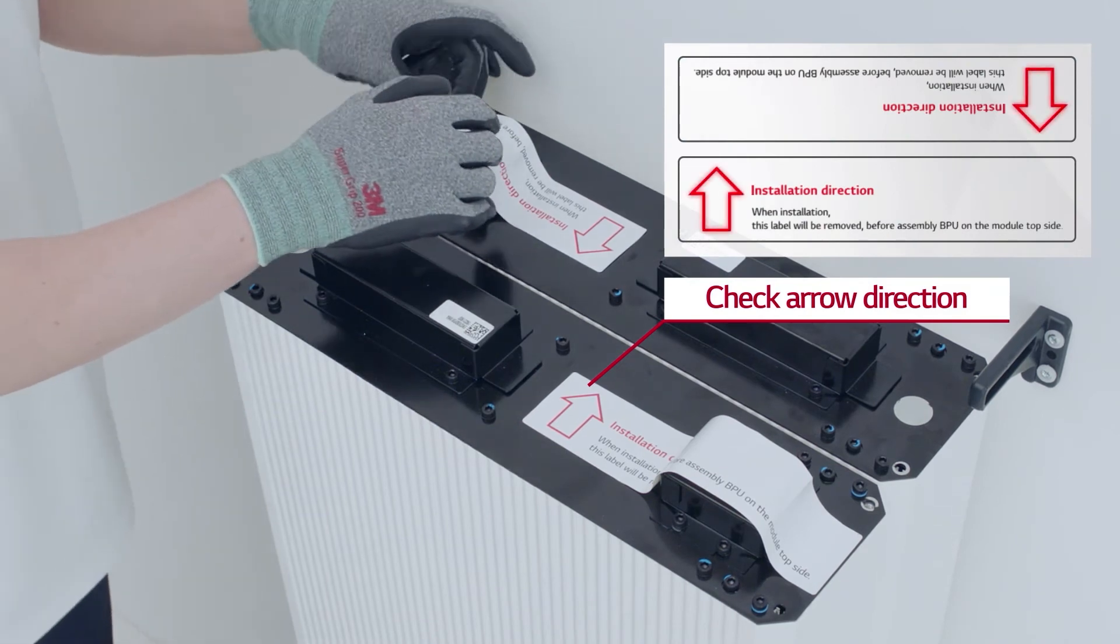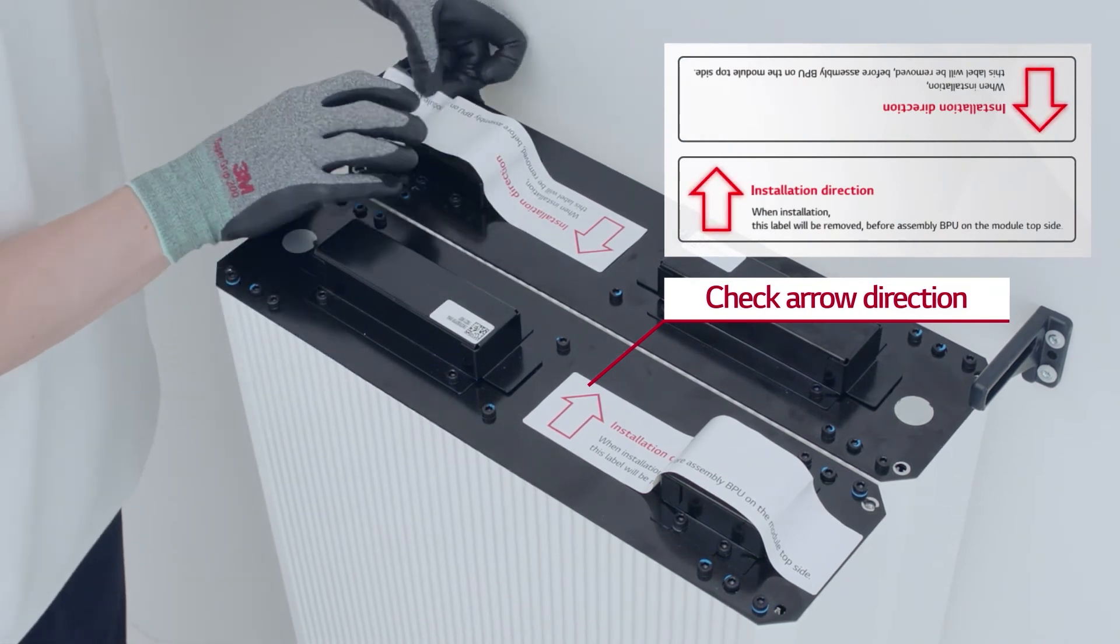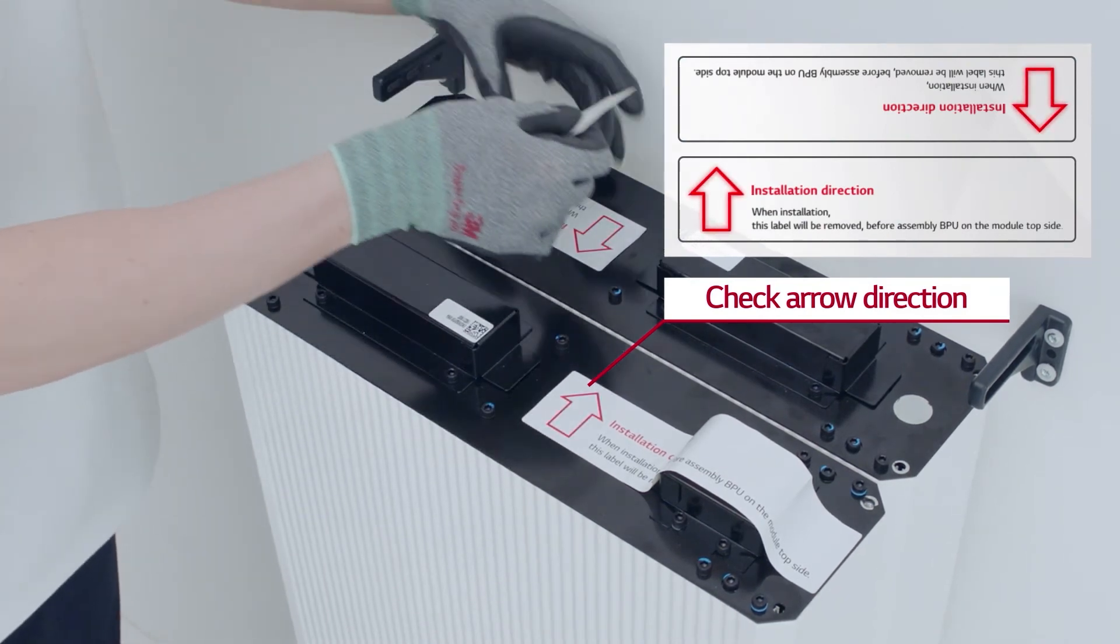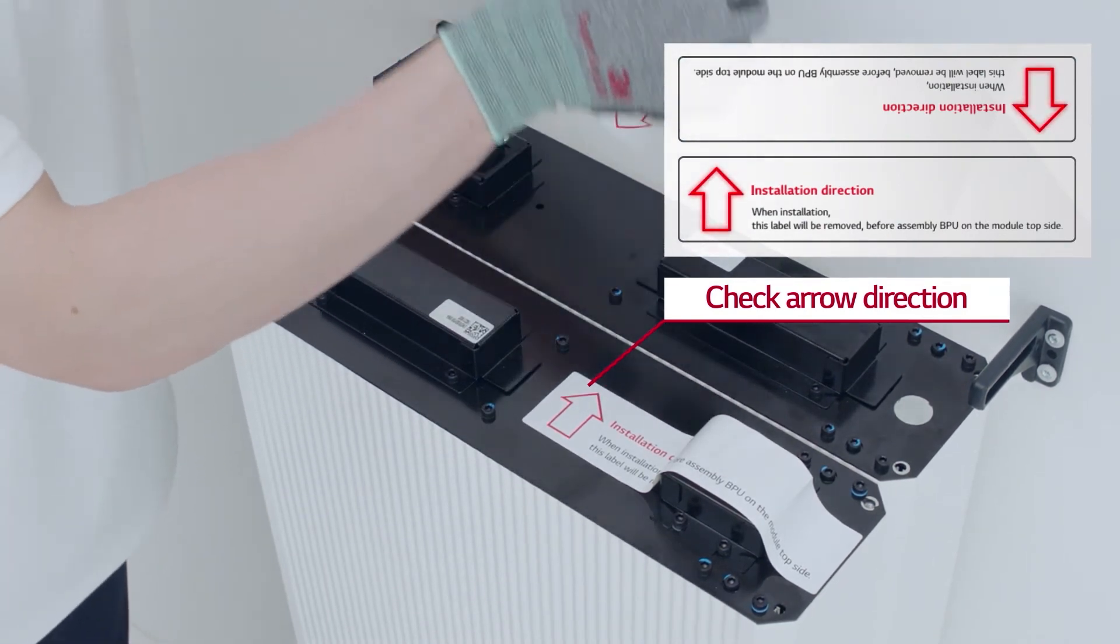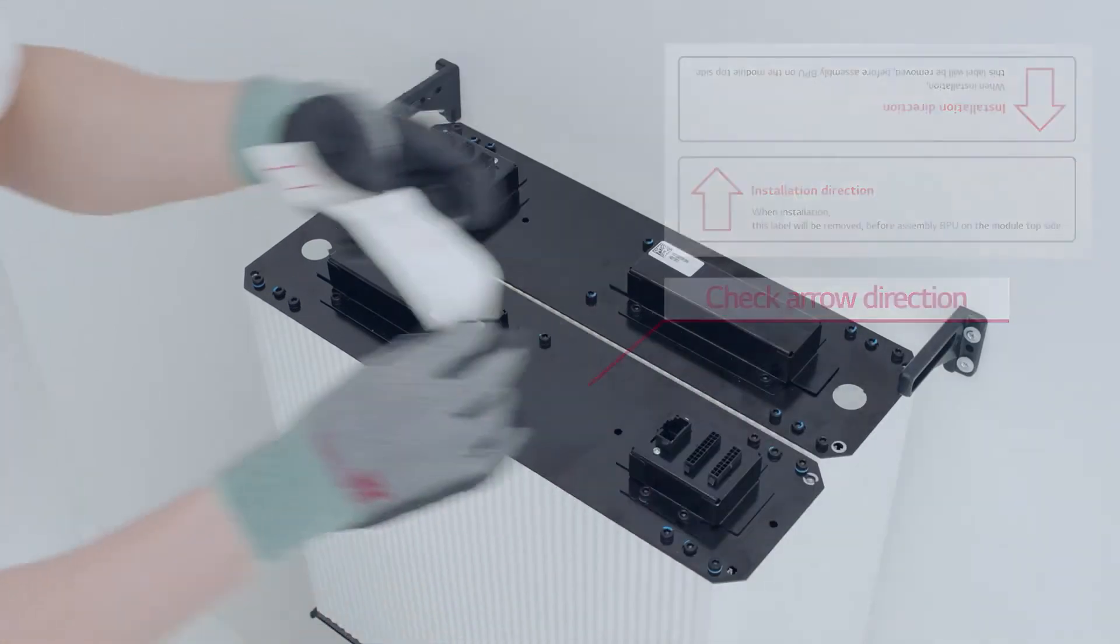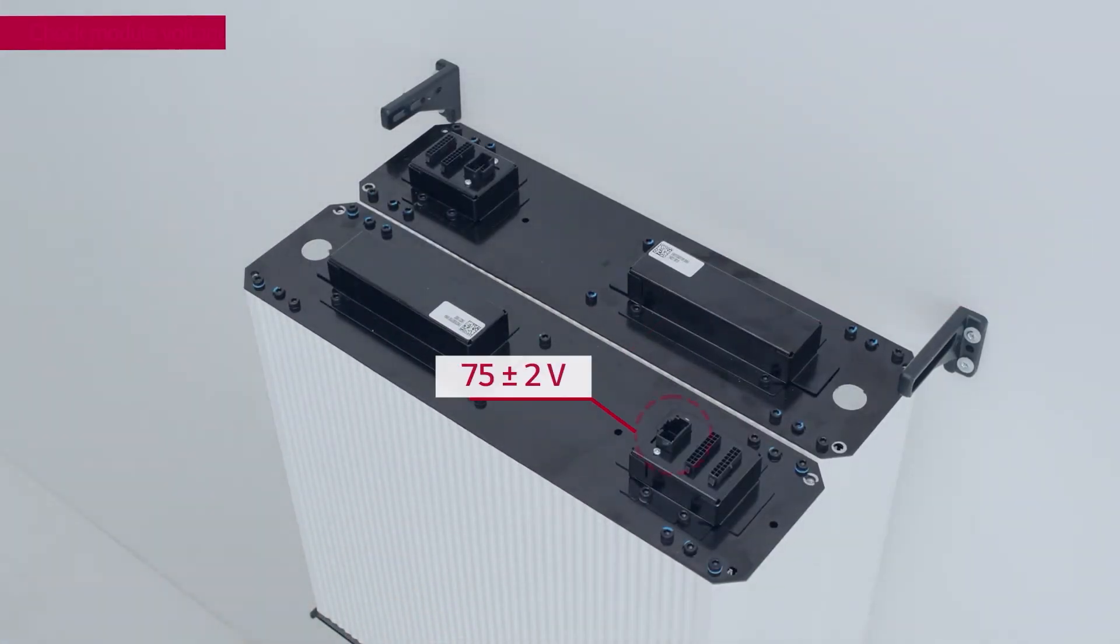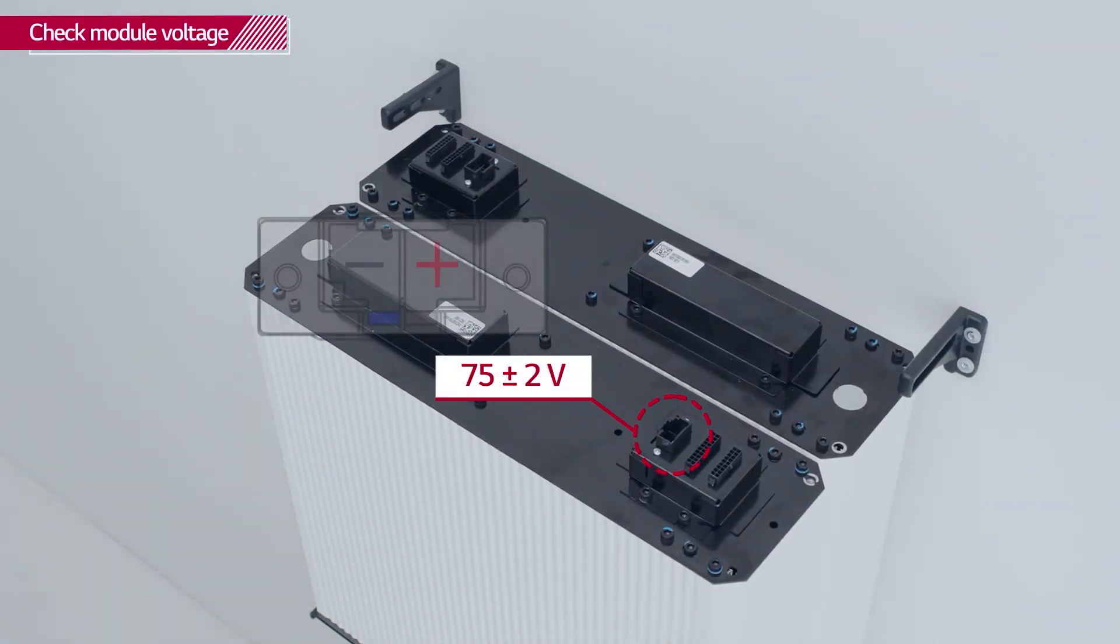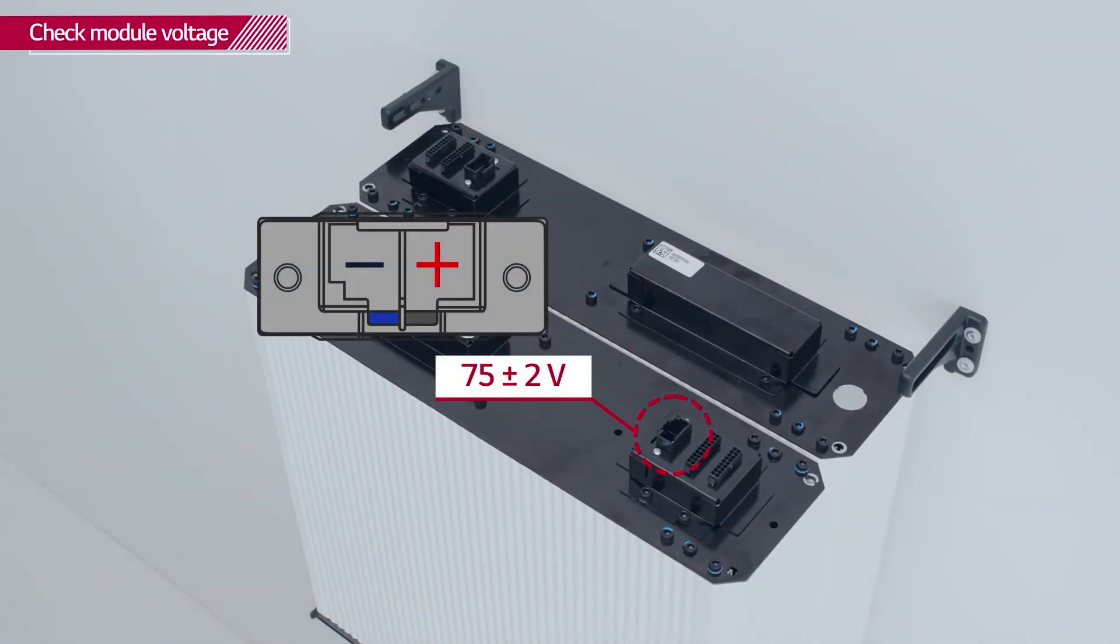Finally, check that the arrows on the connector labels are displayed in the same direction as in the manual and remove the labels. With a voltmeter, check that the module voltage is within 75 plus minus 2 volts range.